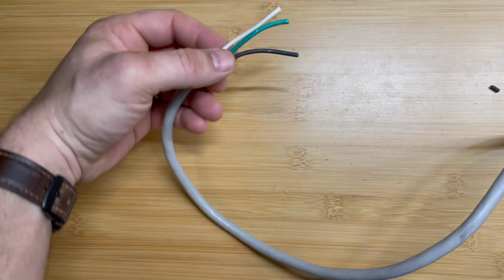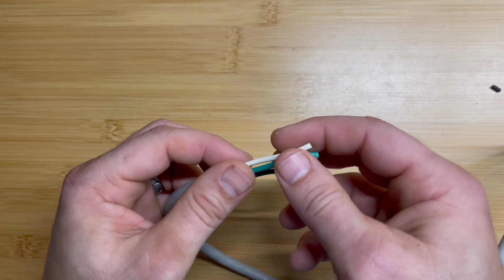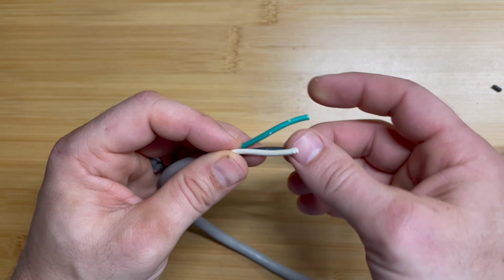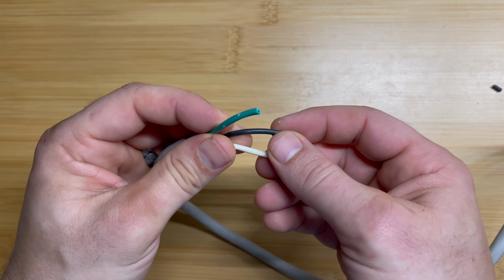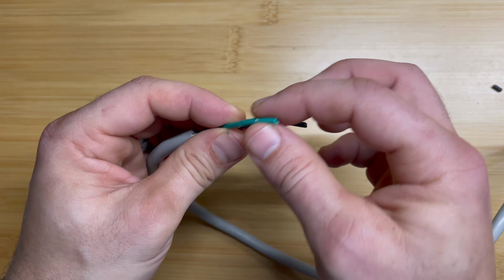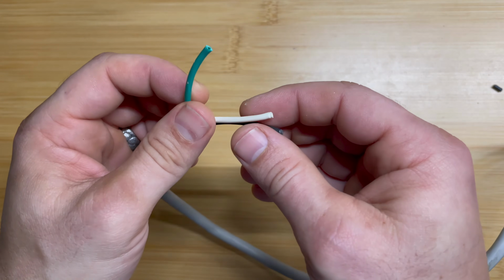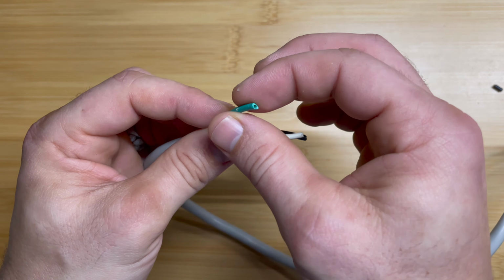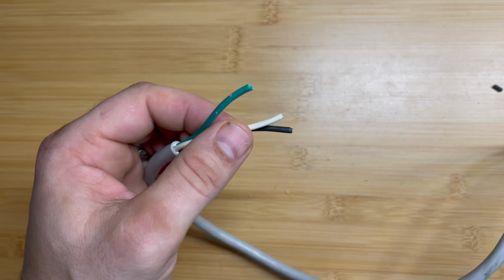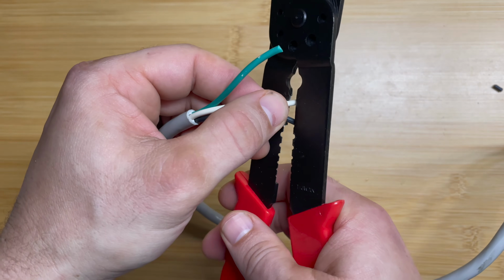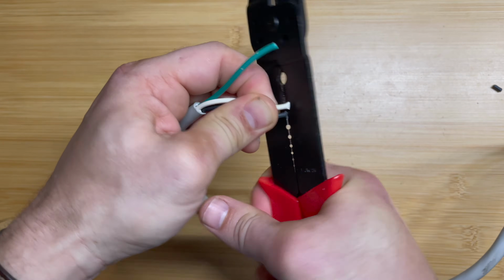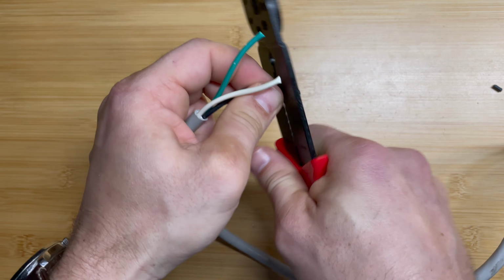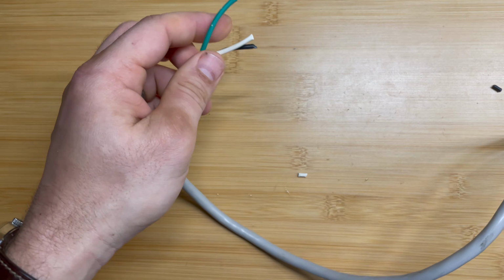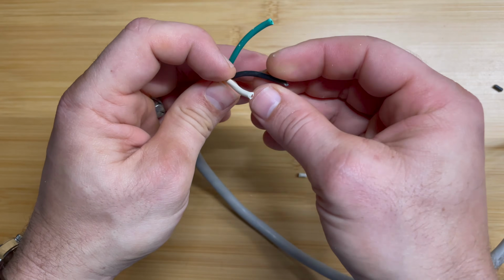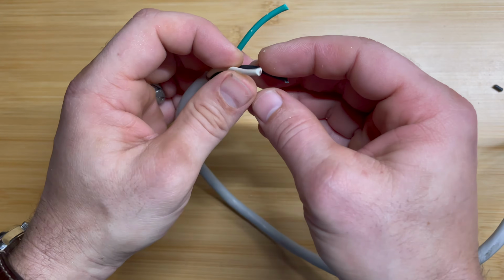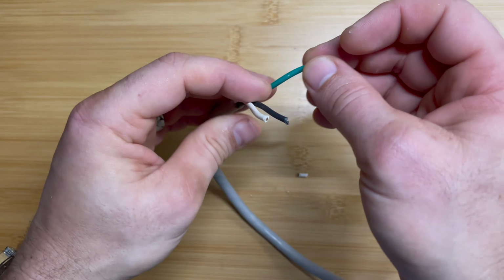The next thing we're going to do is keep our ground wire a little longer than the hot and the neutral. That's because you want this to be the last thing to fail, it's your safety protection, creating a low resistance path to ground. So you want to clip the hot and the neutral just a bit shorter, so that if this cord end does fail, those two wires come out of electrical contact before your ground.